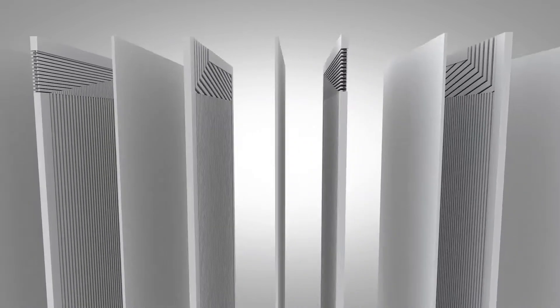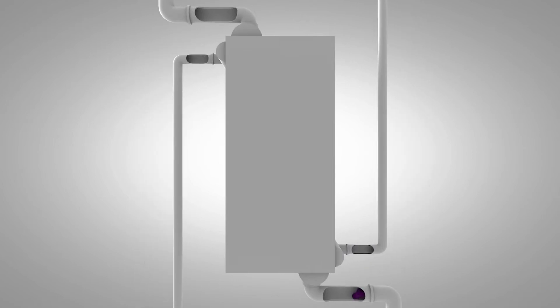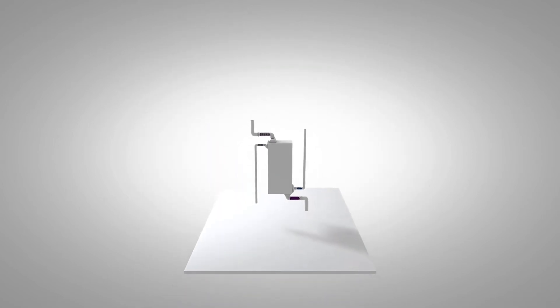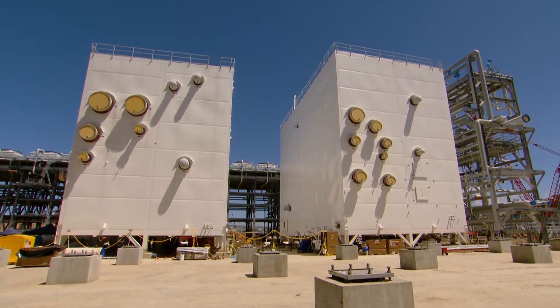The aluminum plates are brazed together. We attach headers to the stack to direct the streams of refrigerants and natural gas, then install all this in a cold box. This heavily insulated box keeps everything cold, giving operators more flexibility during steady and changing conditions.